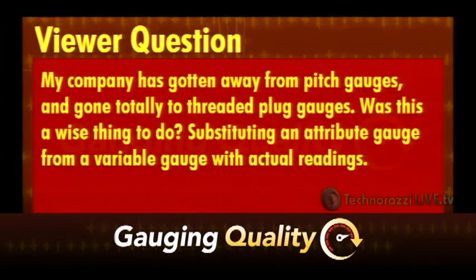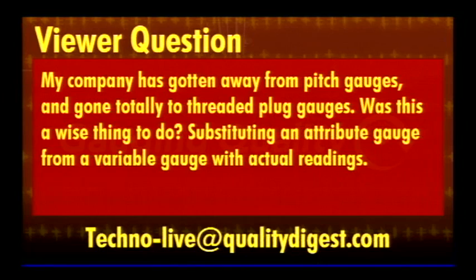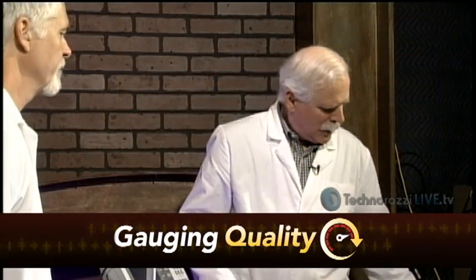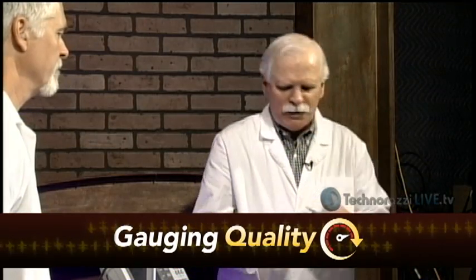My company has gotten away from pitch gauges and gone totally to threaded plug gauges. Was this a wise thing to do, substituting an attribute gauge for a variable gauge with actual readings? There are advantages and disadvantages to pitch micrometers, for instance. So tell me what a pitch gauge is. A pitch micrometer would be a micrometer, but instead of having normal anvils, one will have a V and one will have a cone. And you can check threads at different portions.